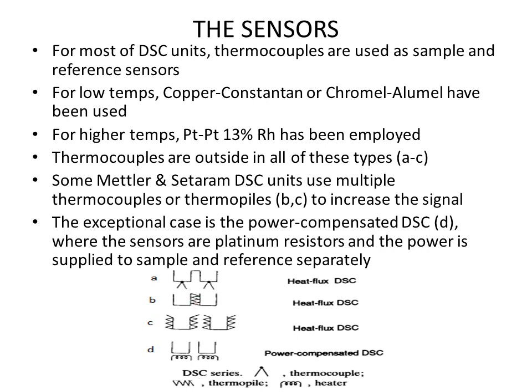Thermocouples are outside the pans, so they are not in direct contact with the sample. Some Mettler and Setaram DSC units use multiple thermocouples, also known as thermopiles, as shown in designs B and C. The purpose of thermopiles is to increase the signal. The one exception is power compensated DSC, shown in design D, where the sensors are platinum resistors and power is supplied to the sample and reference pans separately.